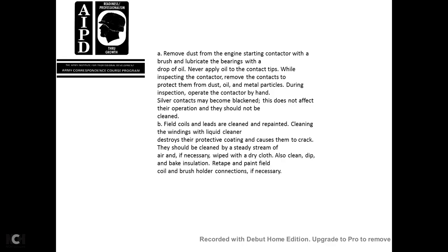Operate the contactor by hand. Silver contacts may be blackened. This does not affect the operation. They should not be cleaned. Field coils and leads are cleaned and repainted. Cleaning the windings and leads with liquid cleaner destroys the protective coating, causing them to crack.